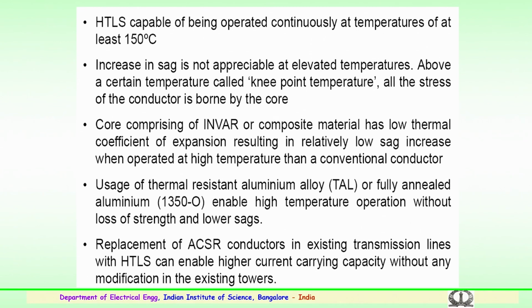So, the replacement of aluminum conductor steel reinforced or AAAC, that is all aluminum alloy conductors or other conductors, in the existing transmission lines with the high temperature low sag conductors will enable the current carrying capability to be increased without any modification in the existing tower. So, this is a very important point when we are going in for operating the existing conductors. It is to be noted that while interchanging the conductors with very high capability HTLS conductors, no modification in the existing towers is required.